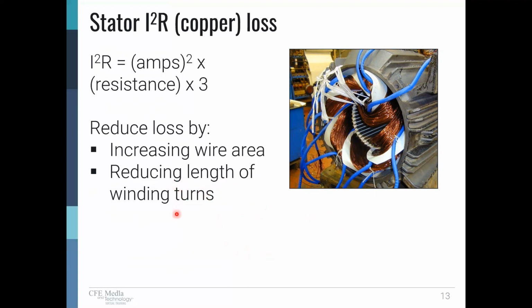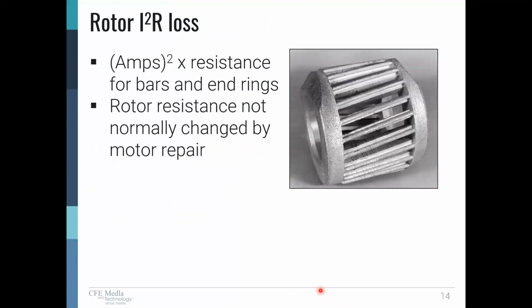If we reduce the length of the turns, then the R in the I squared R formula, the resistance, is lower: the shorter the turns, the less the resistance, similar to increasing the wire area. The larger the wire, the lower the resistance. I squared R loss in the rotor is the amps squared times the resistance of the rotor for the bars and the end rings. And here we see an example of a rotor without a core. Somebody has been able to erode the core away chemically for the purposes of showing us what we have here. So we've got these bars and end rings, and in this case, it's an aluminum material. In larger machines, it might be copper.